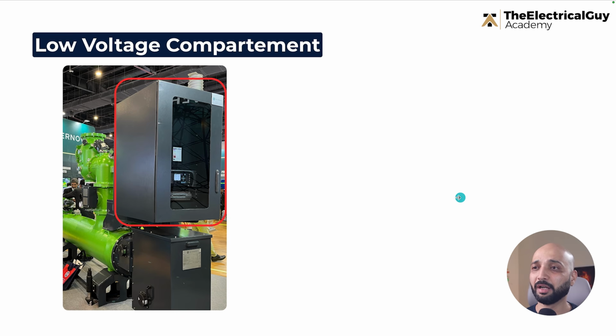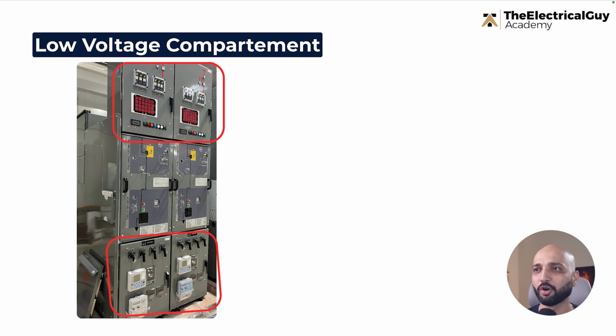And this is an extra high voltage gas insulated type switchgear. I'm not sure exactly whether it is 245 kV or 420 kV, but you can see this is a low voltage compartment. It will have HMIs. It can also have indications and all the other things, basically all the things that you can control from this, right? So that's the low voltage compartment. And not necessarily will it always be on the top. I've seen panels where it is provided on both sides. So you see on top we have the low voltage compartment, and also at the bottom we have a compartment.